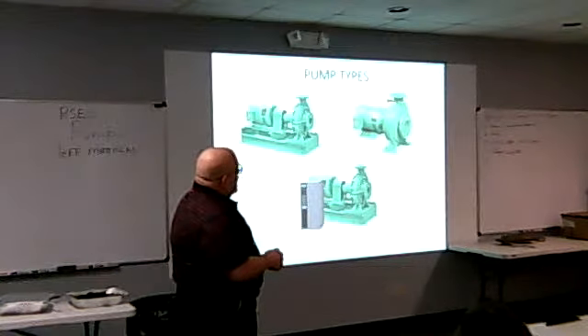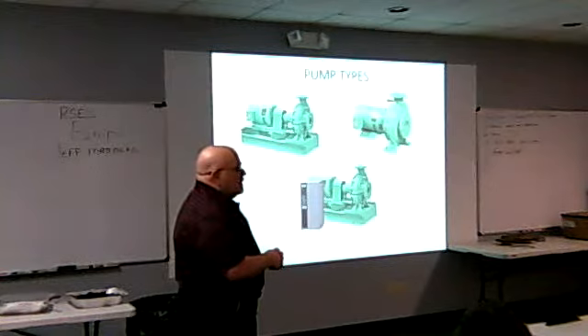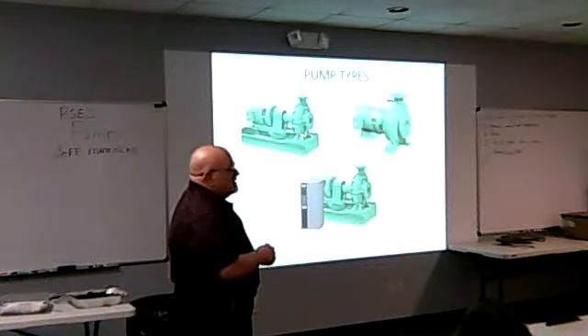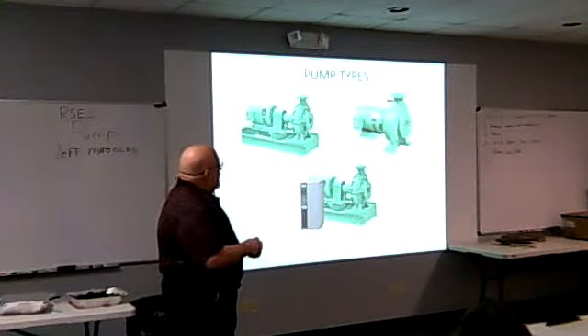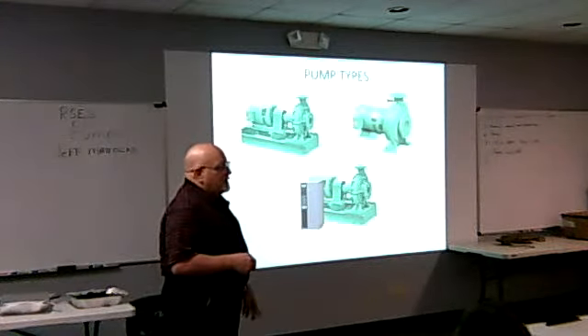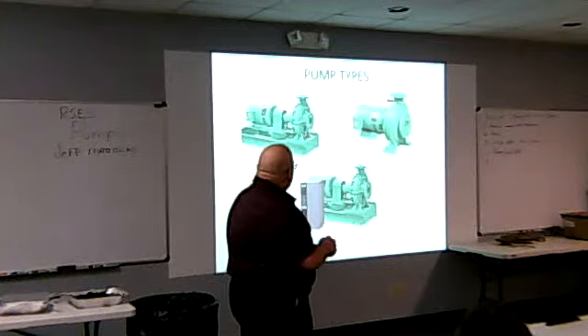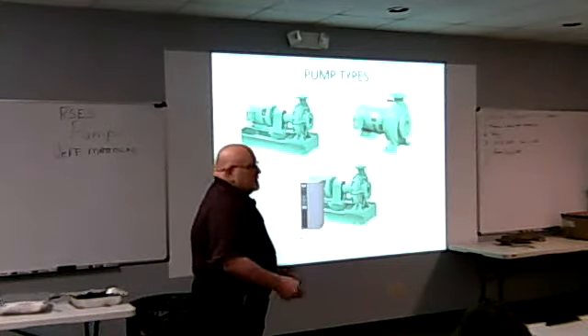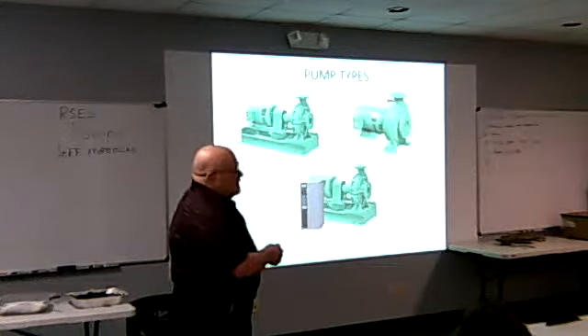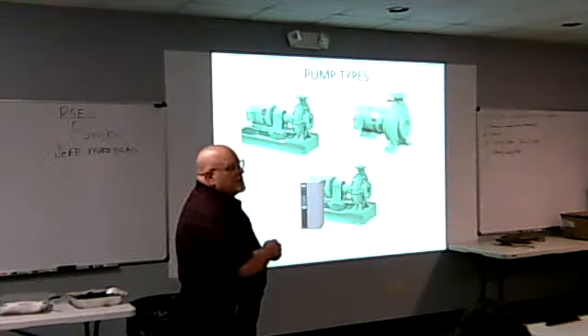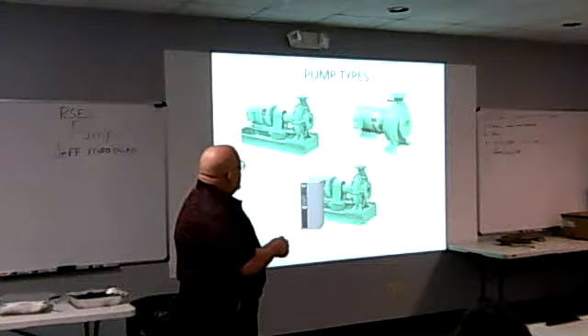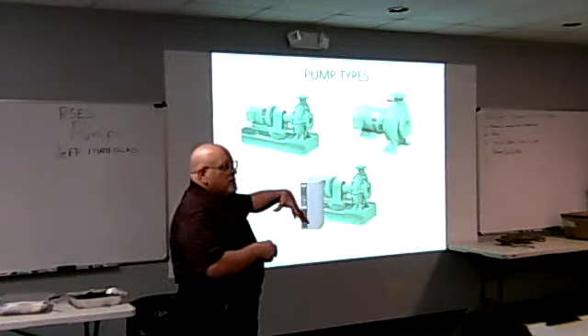This pump here is actually coupled right to a JM shaft motor, and it's tied right to the impeller. The advantage of these is, if I blow a motor here, I have to crack open the water side. This one, I'm not gonna get wet. If I blow a motor, I break the coupling, I have to pick the motor up. Space saving versus easier for maintenance. So these can actually be mounted up on their nose.